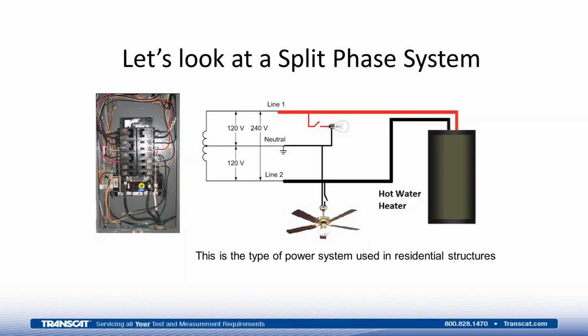We do also have in residential and small commercial 240 volt loads, things like water heaters, ovens, and other type of equipment that would be operated off of 240 volts. So in this particular case, we would bring the L1 and the L2 to the load. That load would then be powered by 240 volts. Some also bring the neutral. It is not required.